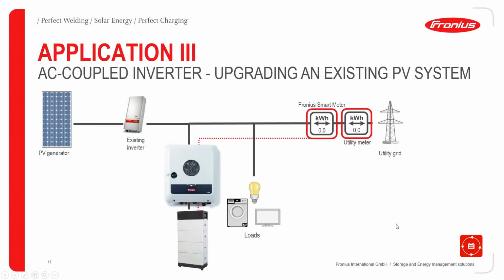Another possibility would be AC coupling with the Gen 24 Plus device. Commonly customers have an existing inverter, which doesn't necessarily need to be a Fronius inverter, it can be another brand, but there is always the option to integrate the storage or the Gen 24 Plus at the AC side. That means AC coupling, and you can also connect the battery to it. That would be another application and an upgrade of an existing PV system, if the customer doesn't want to replace his existing inverter. This is an option we offer from Fronius, which is also possible with our storage combinations.